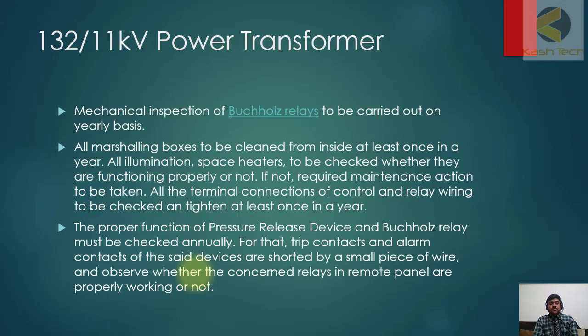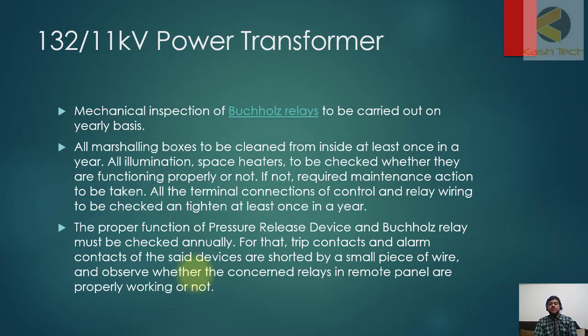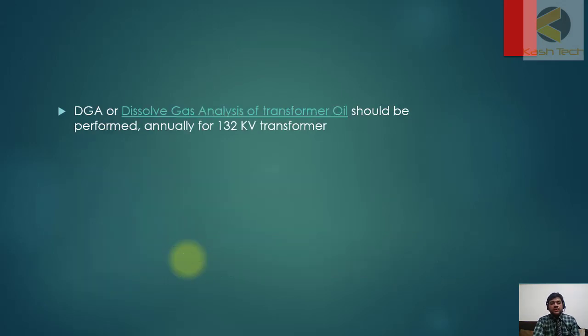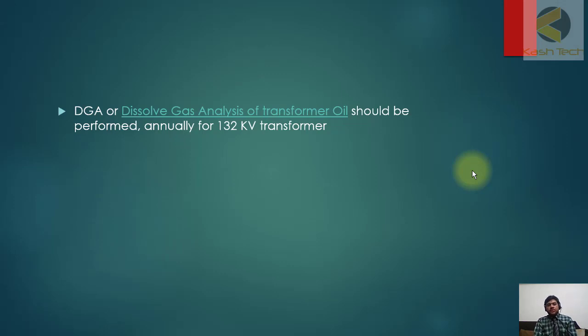The proper functioning of the pressure release device and Buchholz relay must be checked annually. For this, the trip contact and alarm contact of the said devices are shorted by a small piece of wire, or a push button is provided in some cases, and you observe whether the concerned relays and remote panels are working properly.